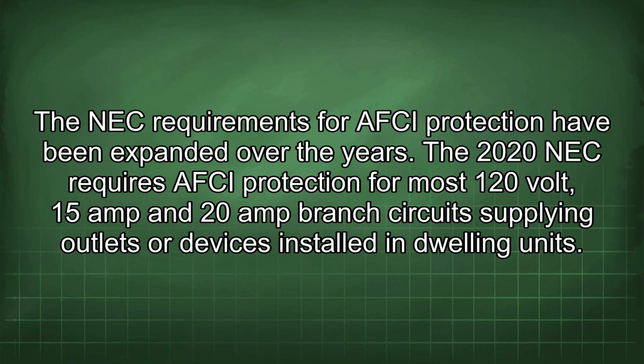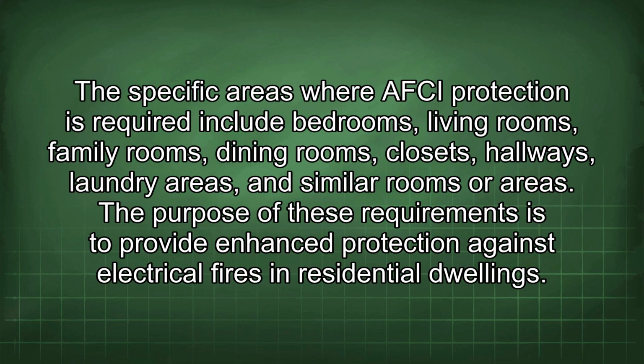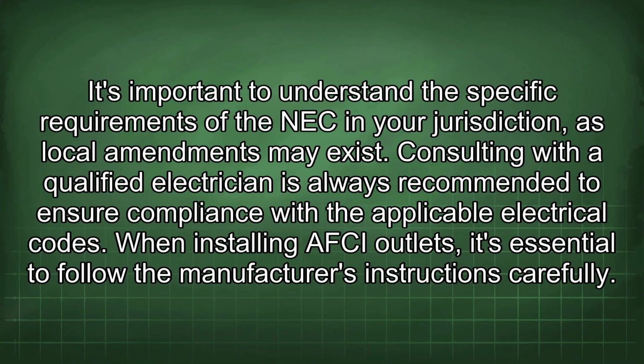The NEC requirements for AFCI protection have been expanded over the years. The 2020 NEC requires AFCI protection for most 120-volt, 15-amp and 20-amp branch circuits supplying outlets or devices installed in dwelling units. The specific areas where AFCI protection is required include bedrooms, living rooms, family rooms, dining rooms, closets, hallways, laundry areas, and similar rooms or areas. The purpose of these requirements is to provide enhanced protection against electrical fires in residential dwellings. It's important to understand the specific requirements of the NEC in your jurisdiction, as local amendments may exist.